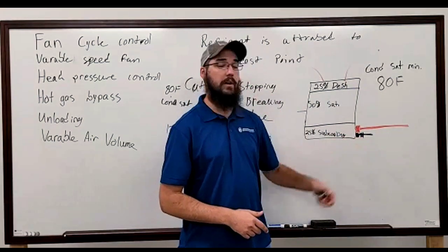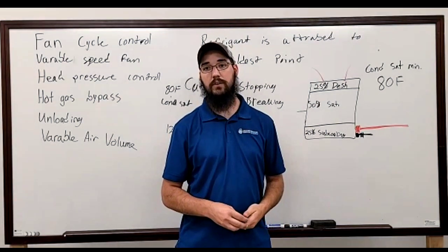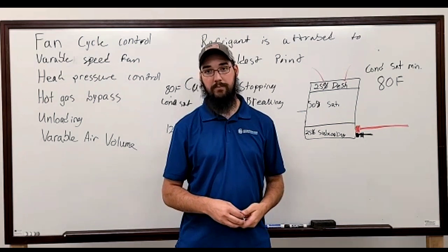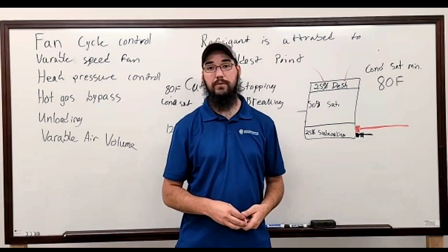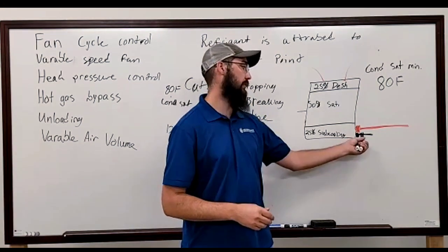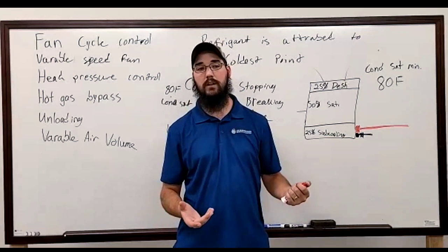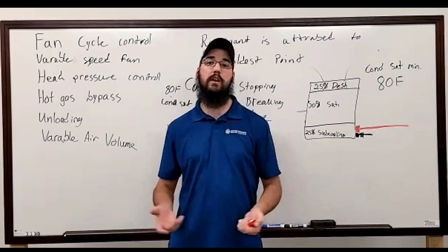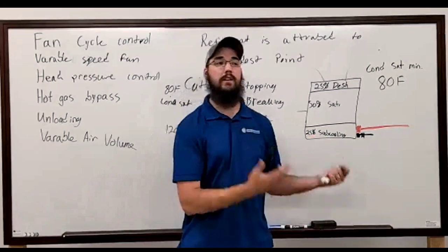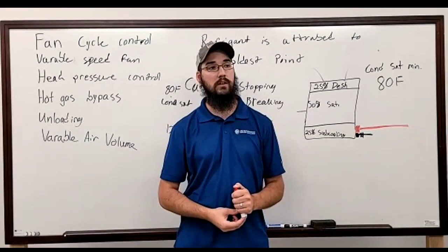To get around this, you have to wire in a fan lockout relay. And this is something you have to do in the field, because these particular pieces of equipment are not specifically designed for commercial applications that need low ambient control.